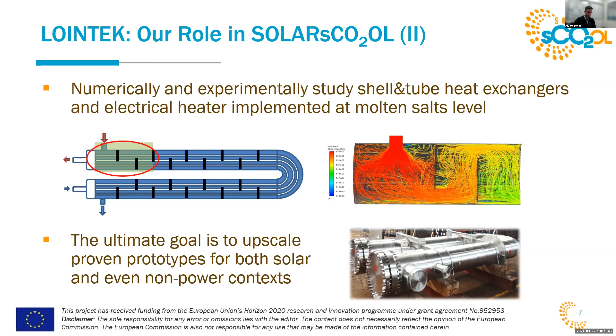In this case, CO2 is a new fluid for us—it will be the first time we both design and operate in supercritical conditions. We are also combining CO2, in the case of the main heater, with molten salts. This is a tricky fluid: very viscous and with a very high freezing temperature. These salts freeze around 260 degrees, so it will be a challenge to combine these two fluids in the shell and tube heat exchanger.